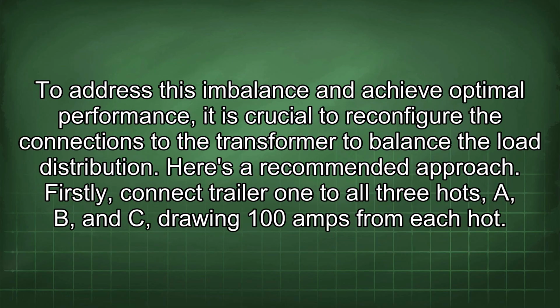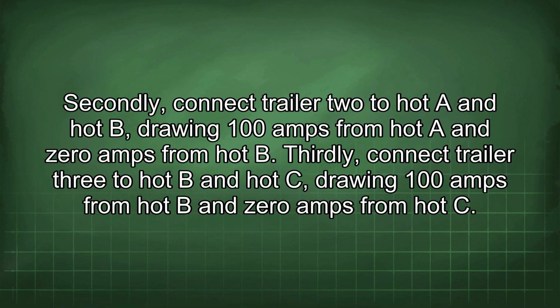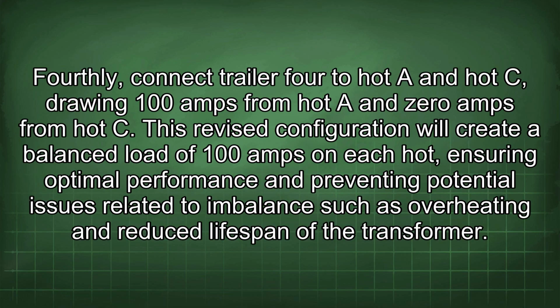To address this imbalance and achieve optimal performance, it is crucial to reconfigure the connections to the transformer to balance the load distribution. Here is a recommended approach. Firstly, connect trailer 1 to all 3 hots A, B, and C, drawing 100 amps from each hot. Secondly, connect trailer 2 to hot A and hot B, drawing 100 amps from hot A and 0 amps from hot B. Thirdly, connect trailer 3 to hot B and hot C, drawing 100 amps from hot B and 0 amps from hot C. Fourthly, connect trailer 4 to hot A and hot C, drawing 100 amps from hot A and 0 amps from hot C. This revised configuration will create a balanced load of 100 amps on each hot, ensuring optimal performance and preventing potential issues related to imbalance such as overheating and reduced lifespan of the transformer.